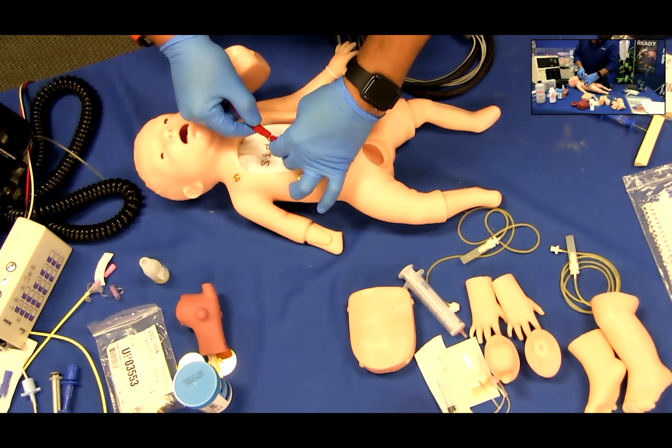To convert, select the initial rhythm to display and then press the convert button. Select the rhythm to display after conversion; this rhythm will be blinking. Shock the mannequin using industry standards for infant defibrillation, using 20 joules of energy, which is enough to convert. Do not go over the industry standard. After shocking Charlie, the blinking rhythm will turn solid on the interactive ECG simulator and will be the rhythm displayed on your defibrillator or monitor.